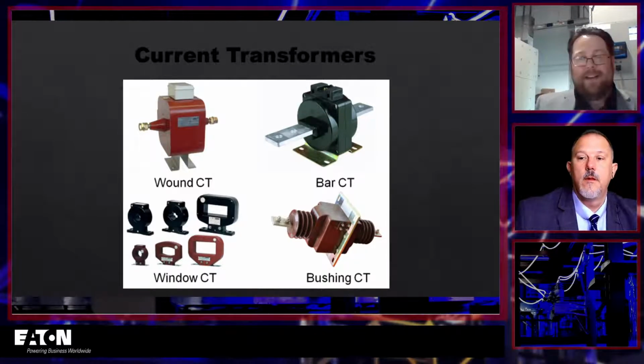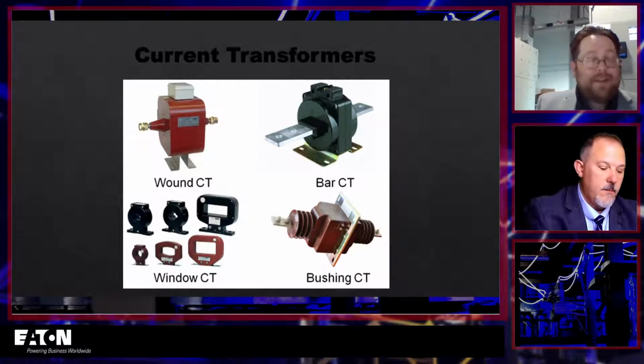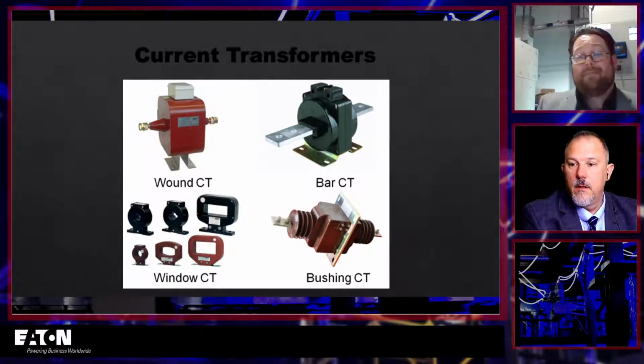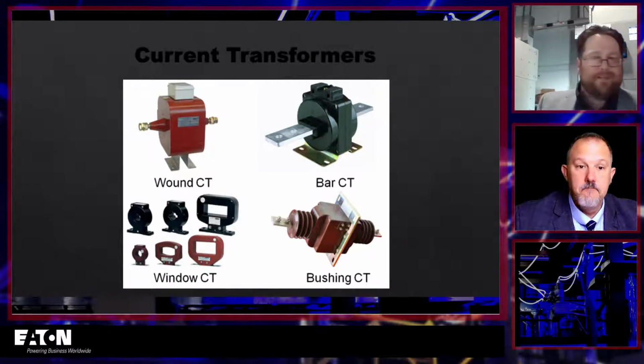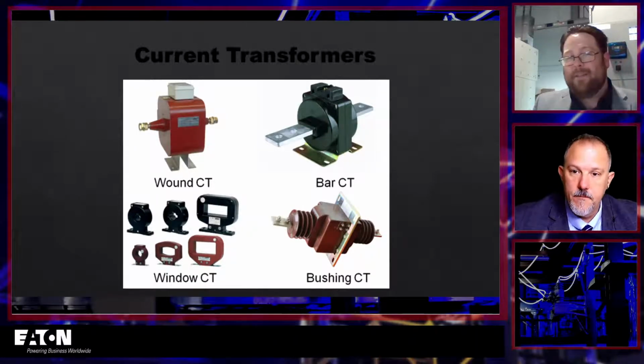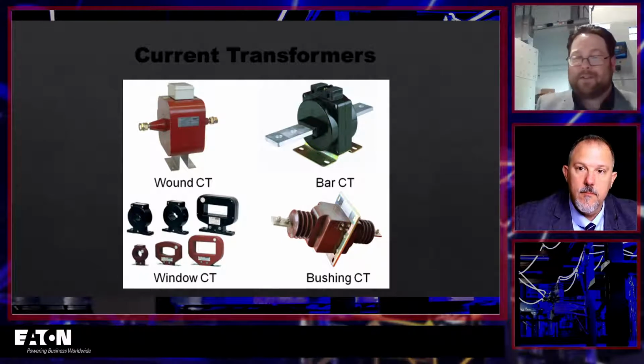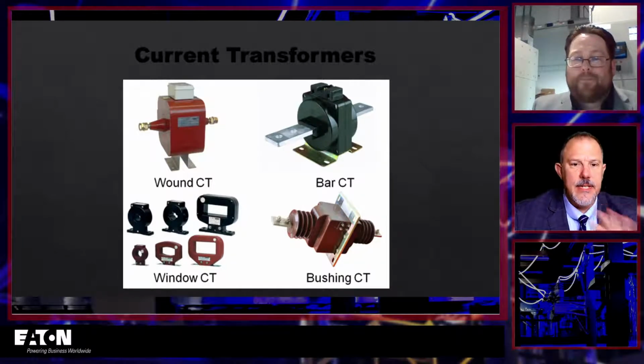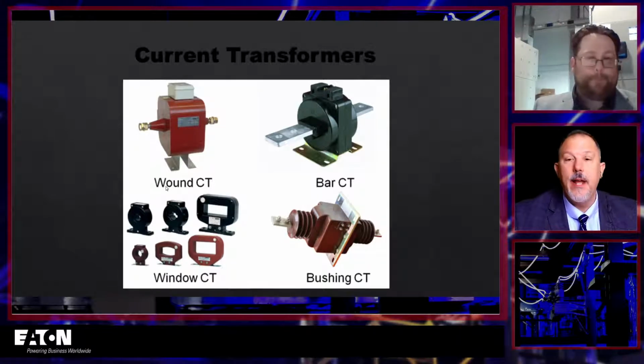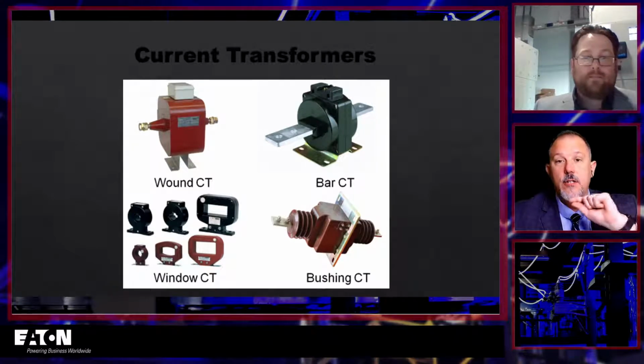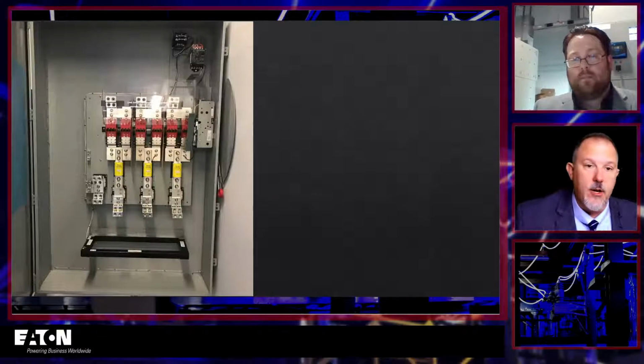Connect your leads on, hit go, and it will actually tell you everything you want to know about that CT. It's just a transformer. It'll tell you the turns ratio, the resistance, is it subtractive, is it additive, all that good information. Nice. Excellent. So it's an easy test to do. You've got to get the right one, and sometimes the CTs are not marked correctly. So you've got to verify that, make sure it's marked correctly, all that good stuff.